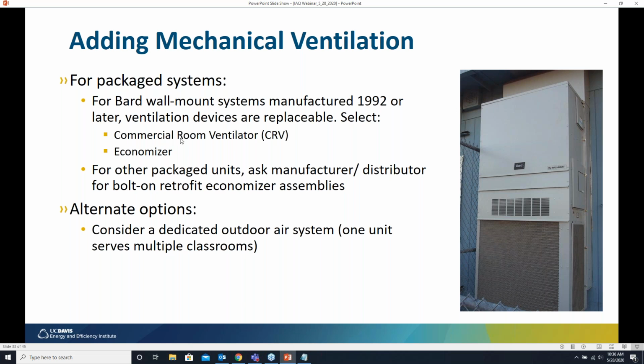Bard has both what they call a commercial room ventilator and an economizer. Both of those can achieve the recommended 400 or 500 cubic feet per minute of ventilation. And definitely consider economizers in most climates in the US, the largest benefits being in the West and the northern climates.